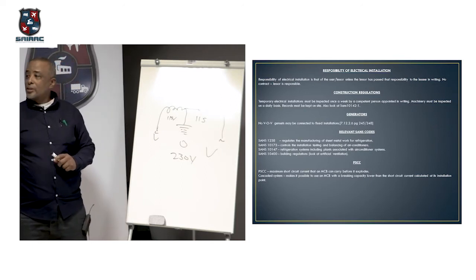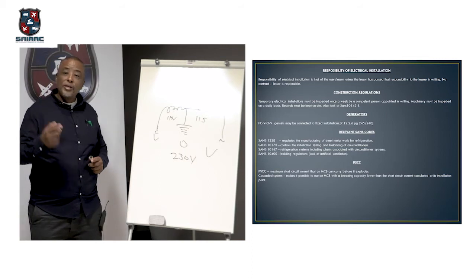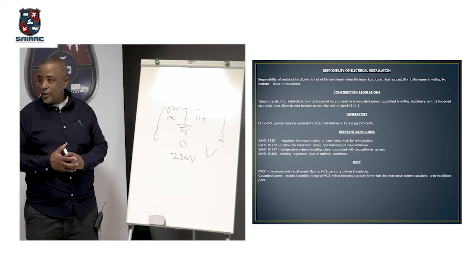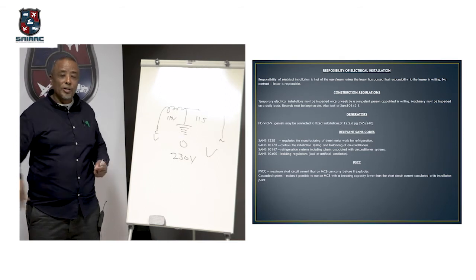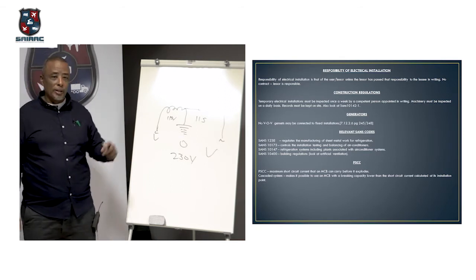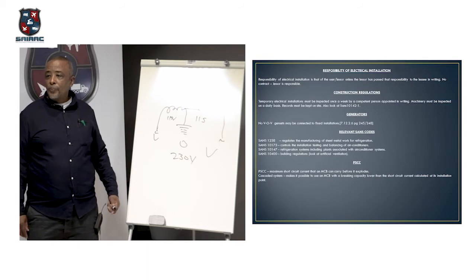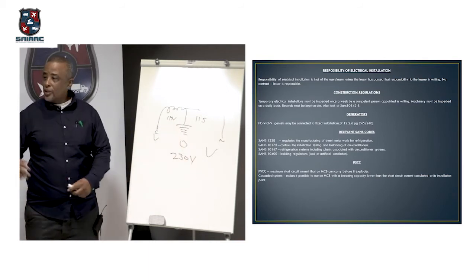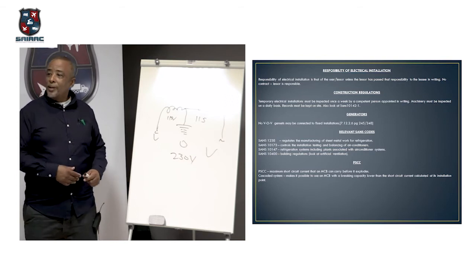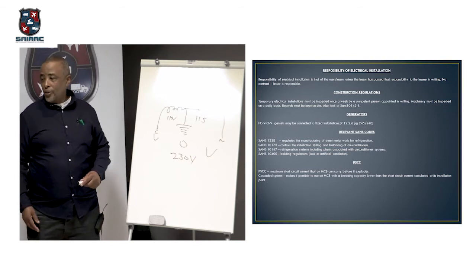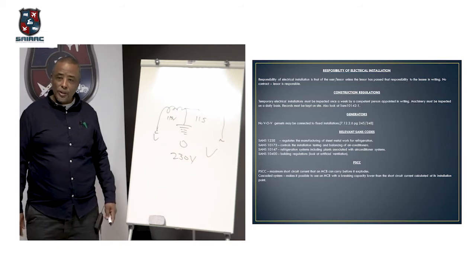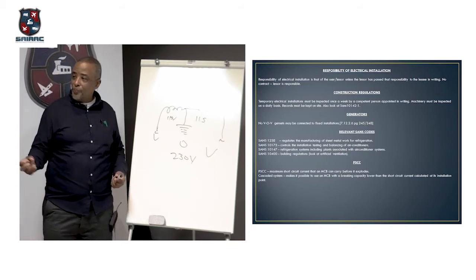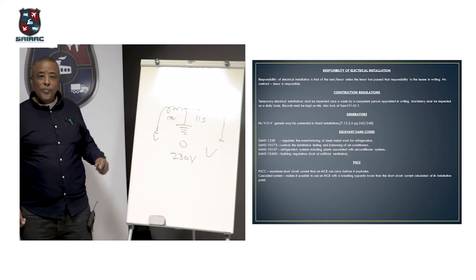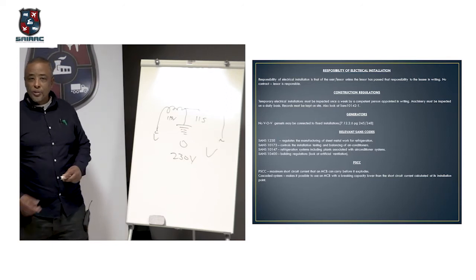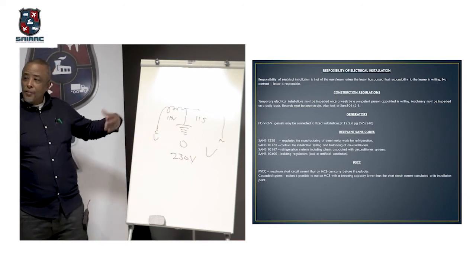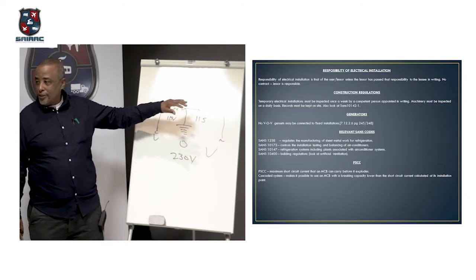there's an Events Act, okay? And the Events Act says that all appliances must be on earth leakage. So unfortunately, if you're having an event and you've got those temporary air conditioners and your deep freezers, it's only there for a little while, it must be on earth leakage. Generally in a factory or in a big shopping center, your deep freezers don't need to be on earth leakage. But that's where the problem comes in. It's not going to pick up leakage problems, and we do get people getting a tinkle from the fridge and that type of thing, or the appliance. I have a lot of call-outs for people getting shocked by taps and that type of thing.